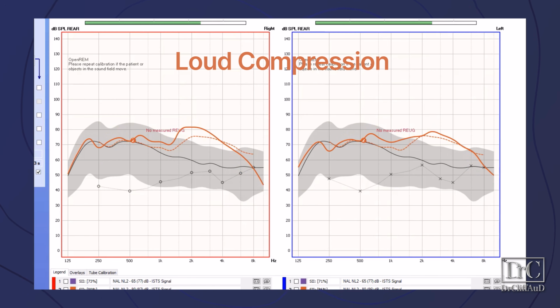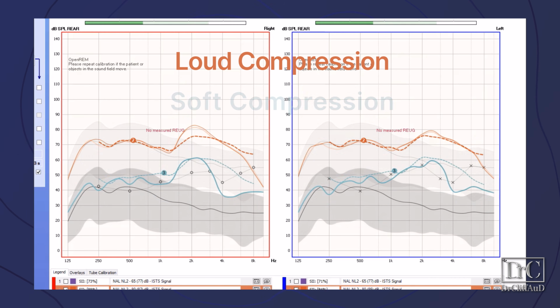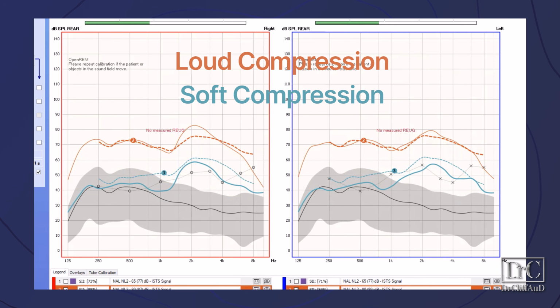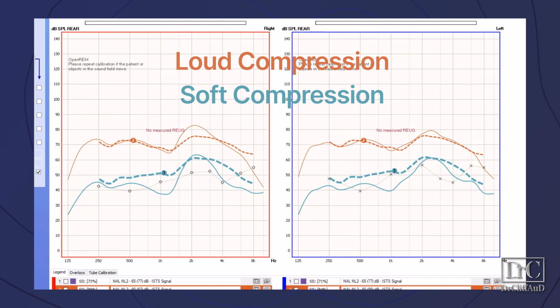While the Lexie B2 Plus devices did a good job of compressing loud sounds as indicated by the solid red line, the soft level compression was not very good as indicated by the solid turquoise line. Essentially, this means that soft level speech would be a big issue, creating problems trying to understand soft talkers. However, because there are no specific compression adjustments, we would not be able to improve audibility of soft level speech without inadvertently over-amplifying average and loud level speech.